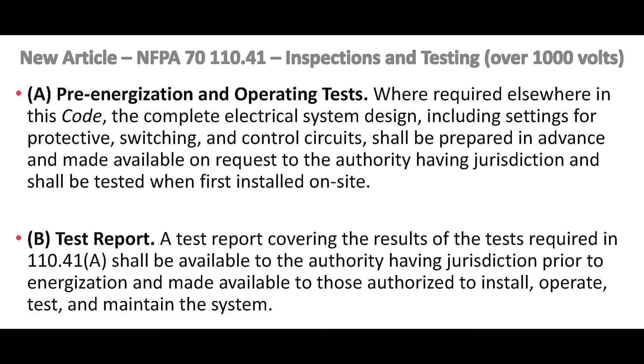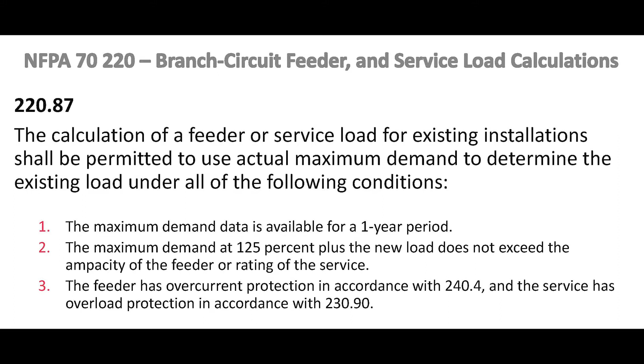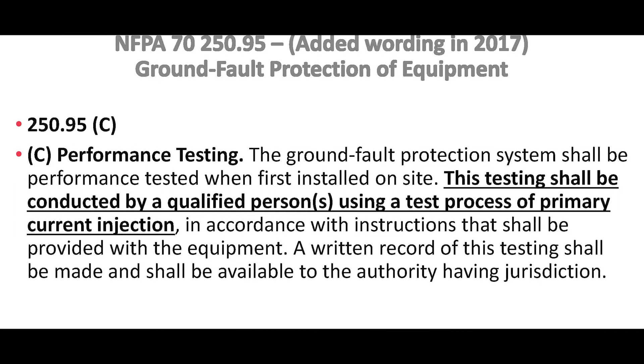Existing NEC requirements here, doing load calculations. If in your building you're going to add a load, by the code, you have to either do an engineering calculation to make sure that you can adequately and safely add the load, or you have to do a load study on the facility to make sure you can add the load. That's all that says. Ground fault protection just simply states that your ground fault protection has to be tested. There's certain size limitations. I won't get into all the weeds with you, but know that if you have ground fault protection at a certain point, it has to be checked and tested.